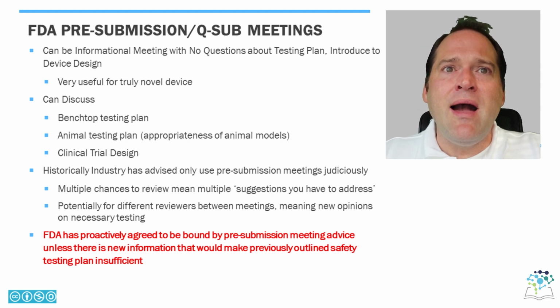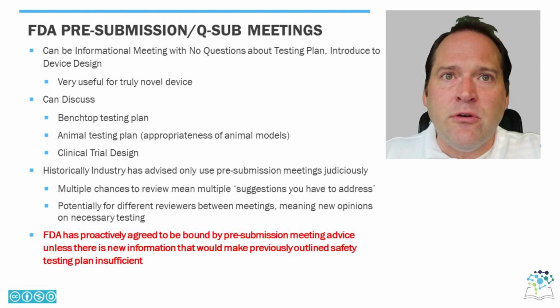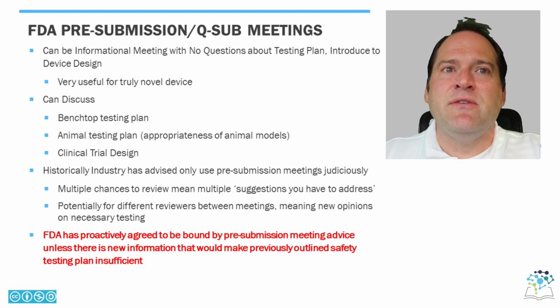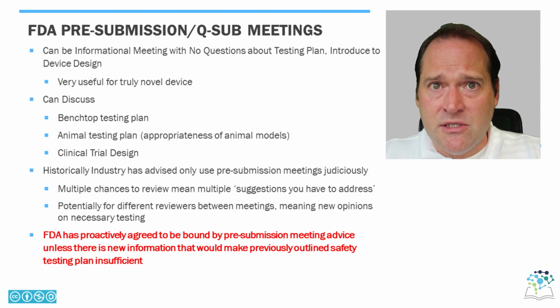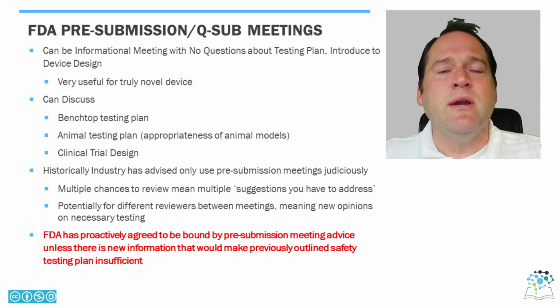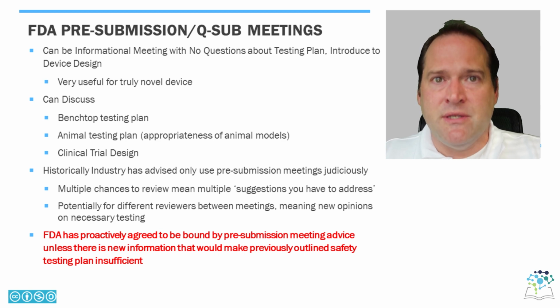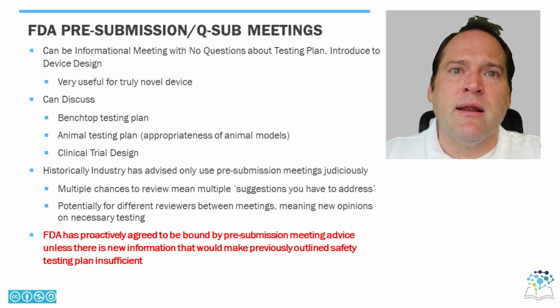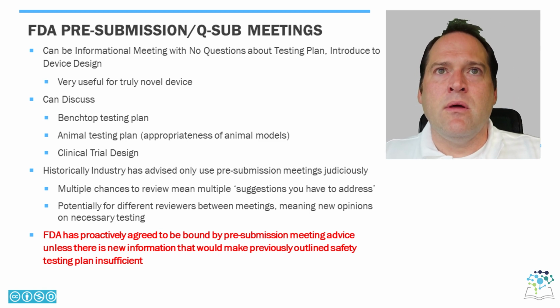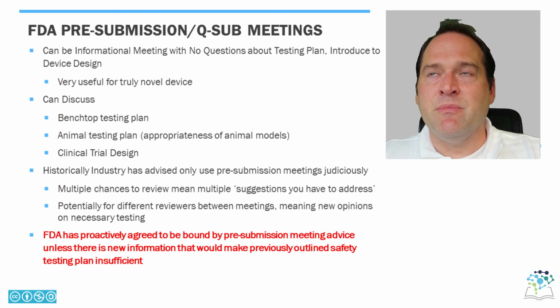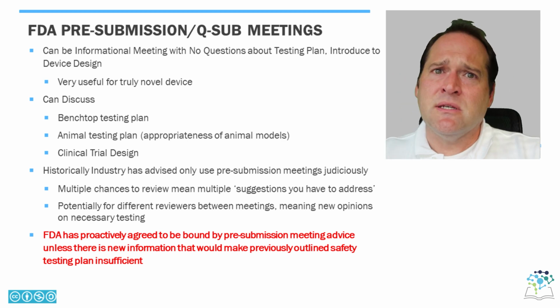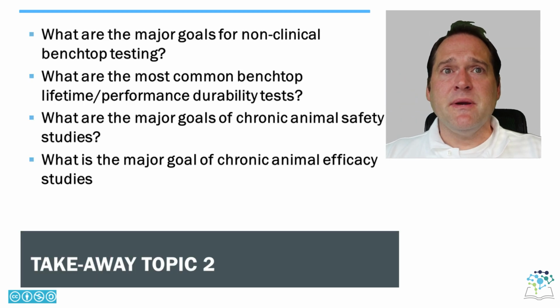Now, the FDA has proactively agreed now to be bound by pre-submission meeting advice unless there is new information that would make the previously outlined safety testing plan insufficient. Now, the FDA does see a lot of testing on a large scale, and so sometimes a new issue occurs that they hadn't thought about in previous applications/submissions, but they become aware of it and they start looking at it. And that's typically now what I see the most often, when the FDA gives one set of advice about testing and then you come back in and they say, hey, can you do this additional test? So that is the end of topic 2.